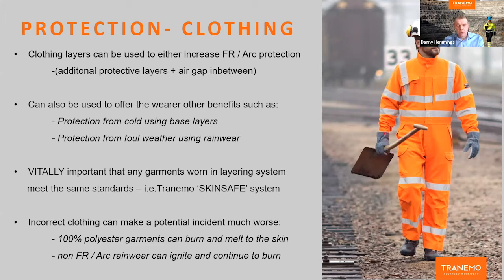The issue there is that if you introduce a layer that's non-complementary or incorrect fabrics, you can end up making a potential incident much, much worse. An example of that could be a 100% polyester garment worn under a flame retardant arc jacket. The temperature or the thermal effects could still lead to that polyester underneath the outer layer burning or melting to the skin from the inside. Equally, if you wore just a standard high-vis jacket in an arc flash, that would just ignite and it would continue to burn, and the residue and the debris would stick to the workwear. So, of course, then it's compromising the protection that the workwear needs to offer in the first place.